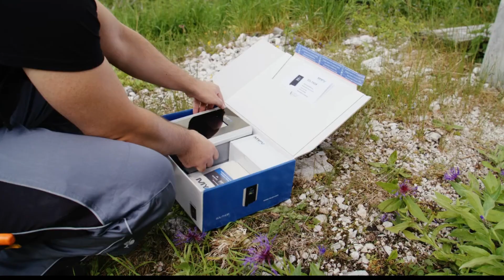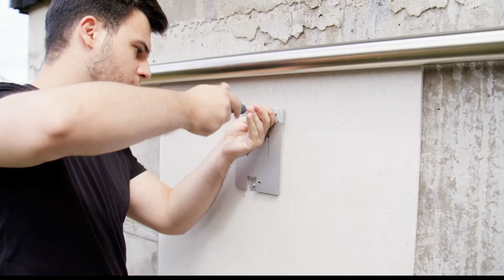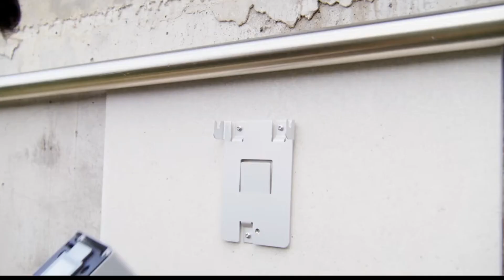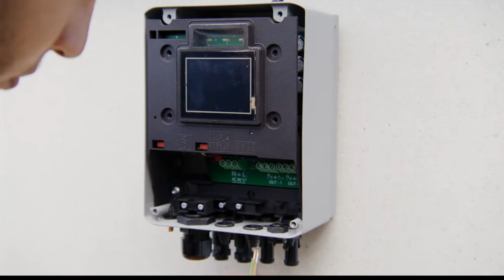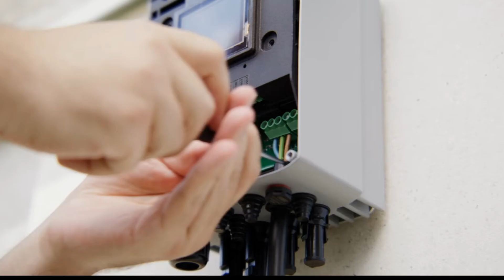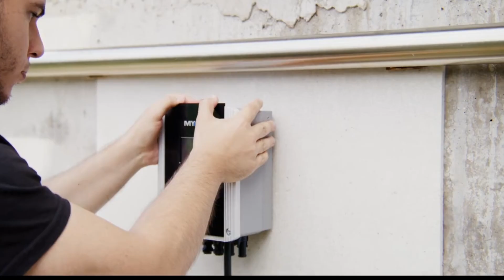The THOR is a DC power manager for solar electric heat generation. Thanks to its autonomous functionality, the THOR does not require a connection to the power grid, as the device is self-supplied by the PV generator. The THOR also scores points for its simple installation. The photovoltaic direct current power manager is simply hung in the supplied wall mount, while the heating element is installed separately in the heat storage tank.